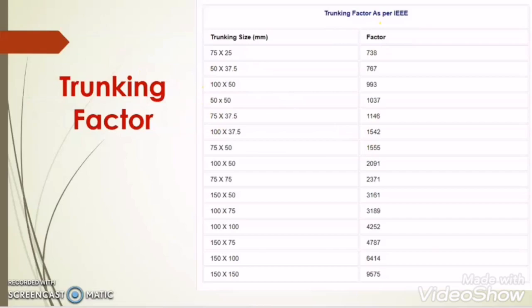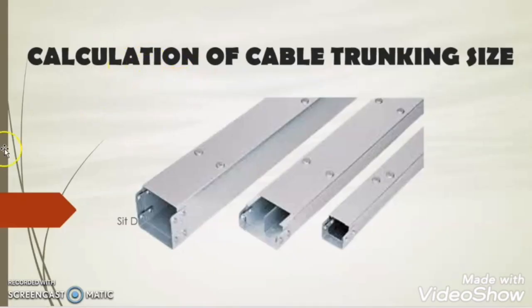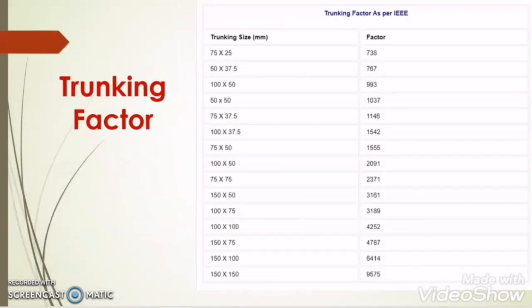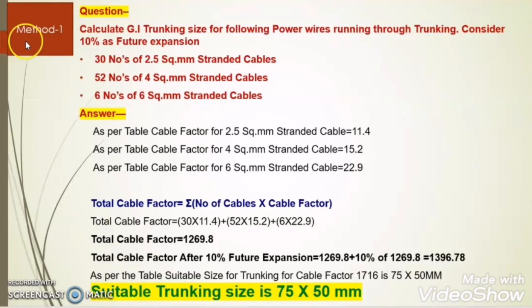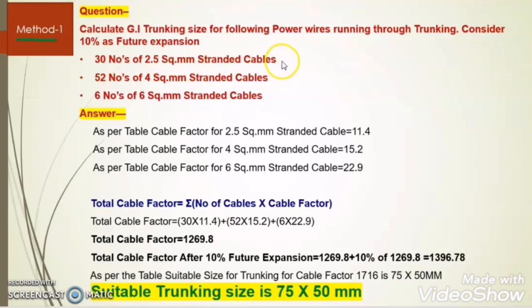In order to better understand how to calculate the trunking size, let us take an example. By referring this chart, we will find the trunking size. Calculate the GI trunking size for the following power wires running through trunking. Consider 10% as future expansion: 30 NOS of 2.5 sq mm, 52 NOS of 4 sq mm, and 6 NOS of 6 sq mm stranded cable.